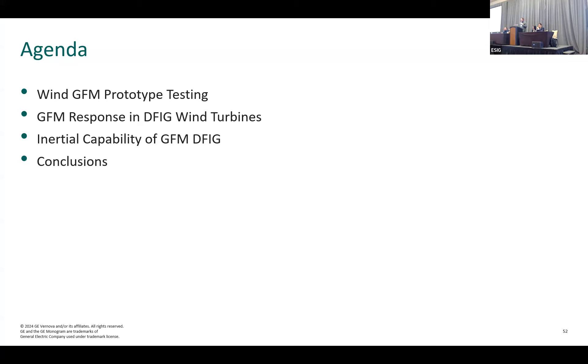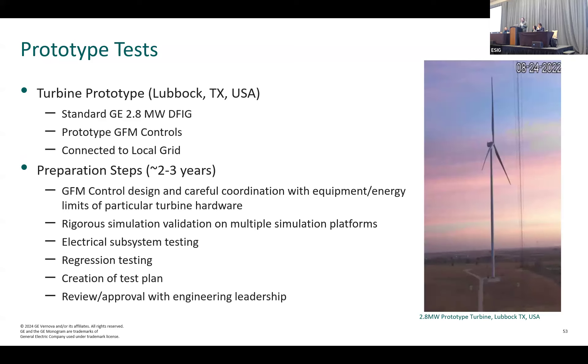What is the expected grid-forming response of these DFIG wind turbines, and we'll discuss the inertia and inertial capability. GE has been working over the last few years on a standard 2.8 MW turbine — one of our workhorse wind turbines — and we've started implementing prototype grid-forming controls on top of that. The prototype we have is in Lubbock, Texas, connected to the local grid — not a grid emulator — it's an actual wind turbine running that can be turned into grid-forming mode.